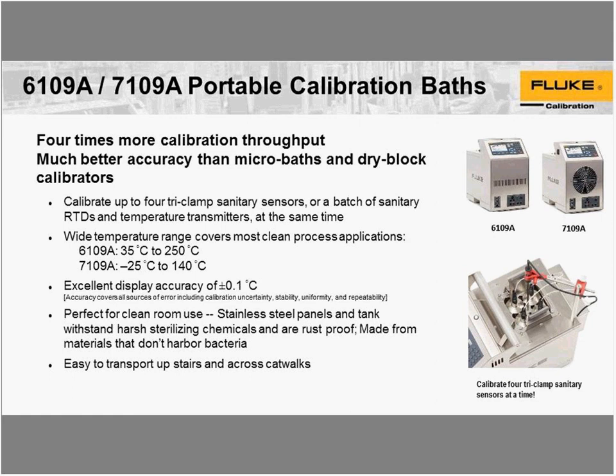They have a tank, and if you can see on the right-hand side here, the lower picture shows 4 sanitary sensors and a reference temperature sensor in the tank. So you can increase throughput, first of all, and have a wide range that covers the needs of these calibration processes. As we went out and visited with this type of instrumentation, this temperature range covers definitely the majority of needs in factories. The 6109A goes from 35 degrees up to 250 degrees, and then the 7109A goes down to -25 and up to 140.